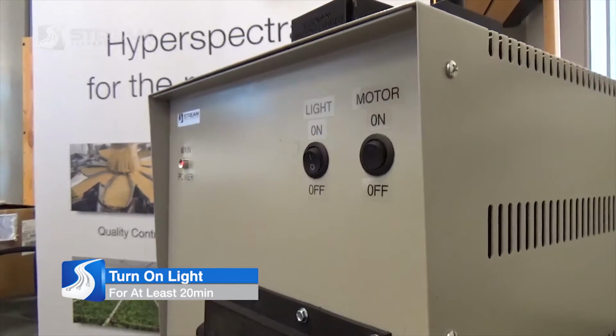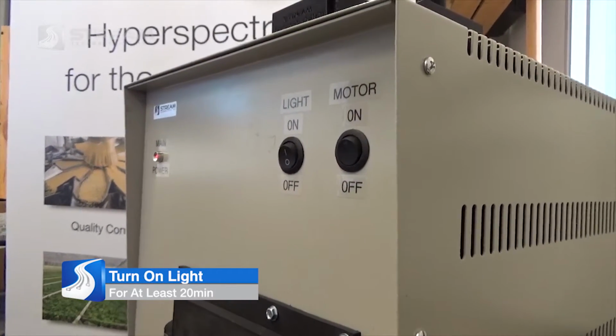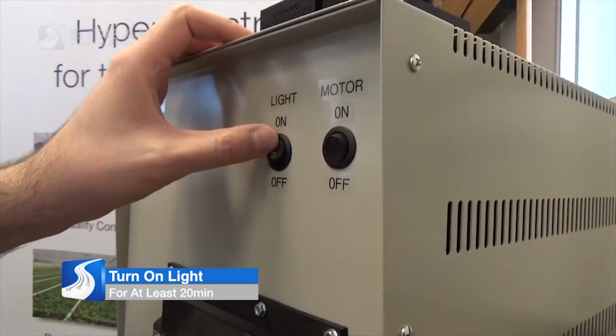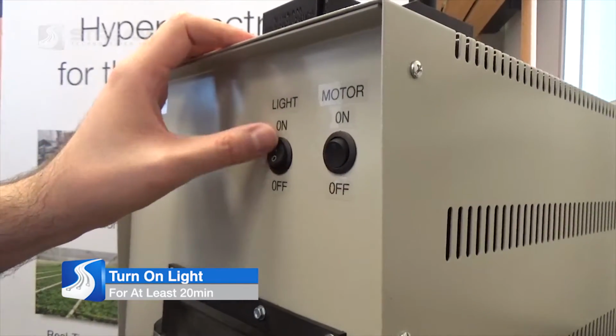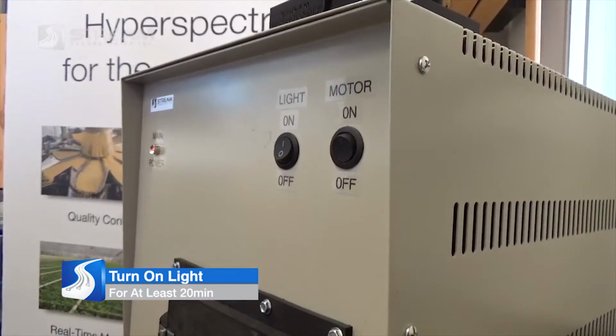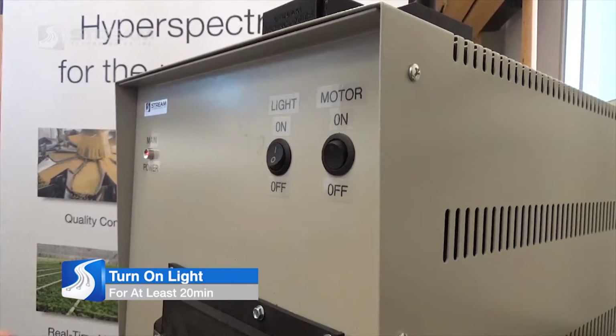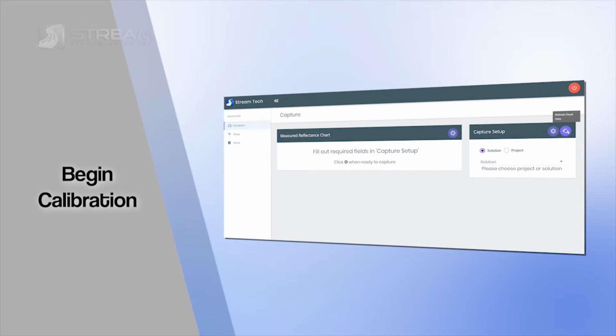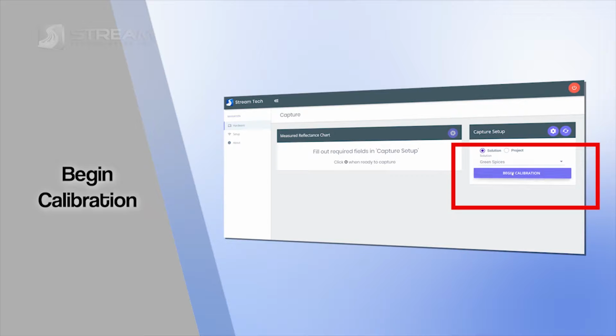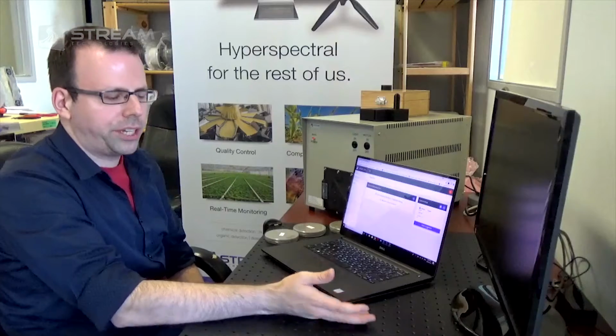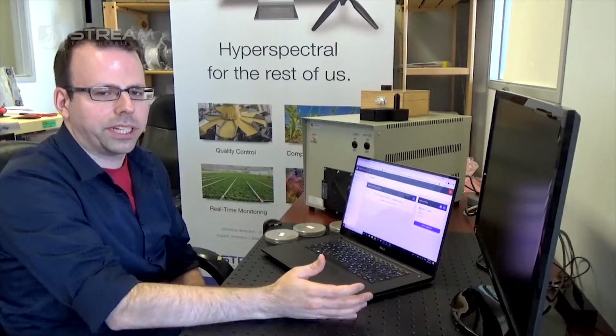So before you start scanning, it's important to turn the light on in the LabFlow box for at least 20 minutes before your measurements start. This is to let the light source warm up and stabilize so that you get a nice consistent spectrum for all your measurements. First we'll need to begin calibration. We need to calibrate the LabFlow box using calibration standards. This is so that results measured in one LabFlow box will be applicable to other LabFlow boxes.